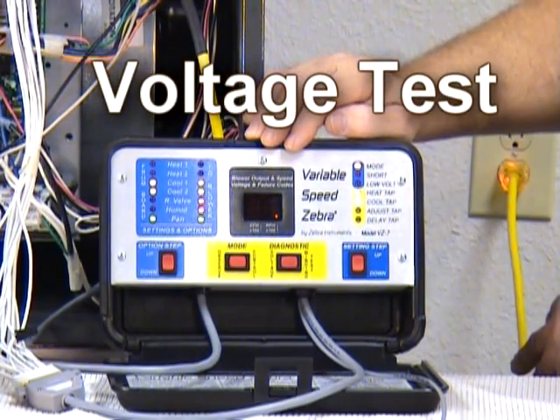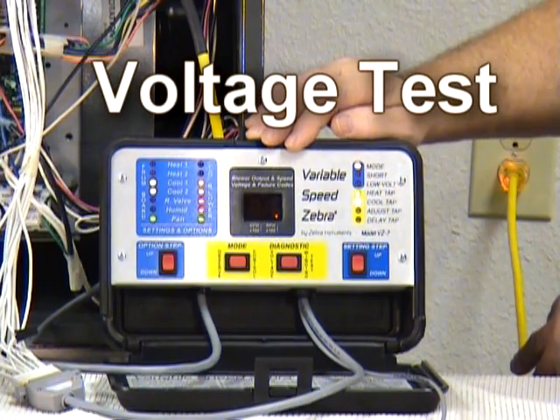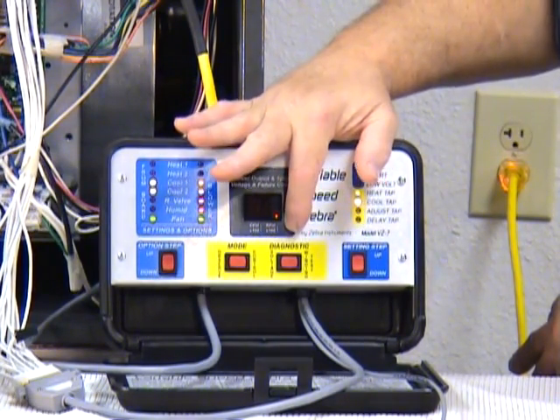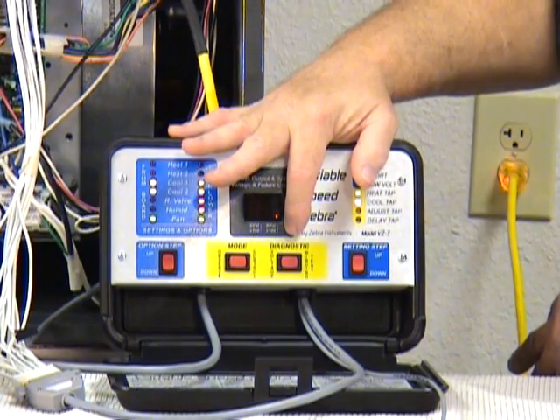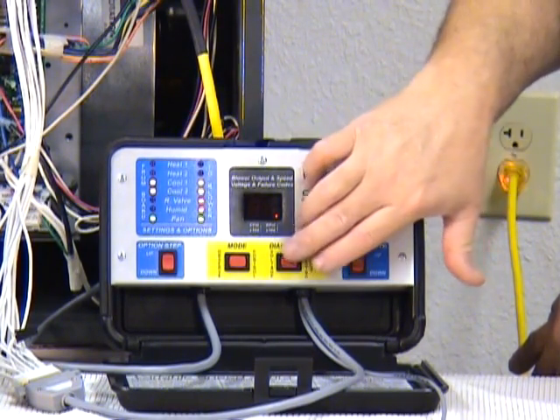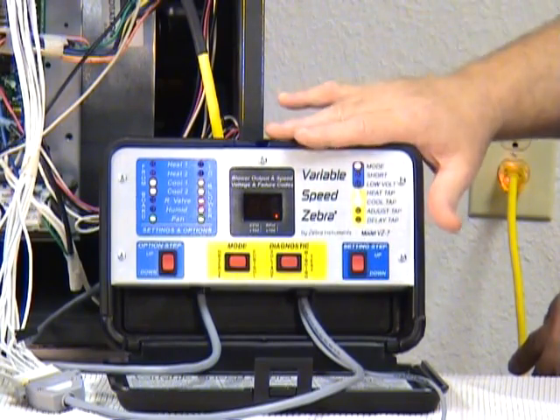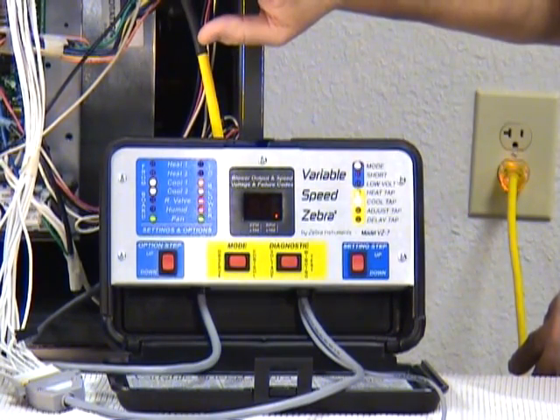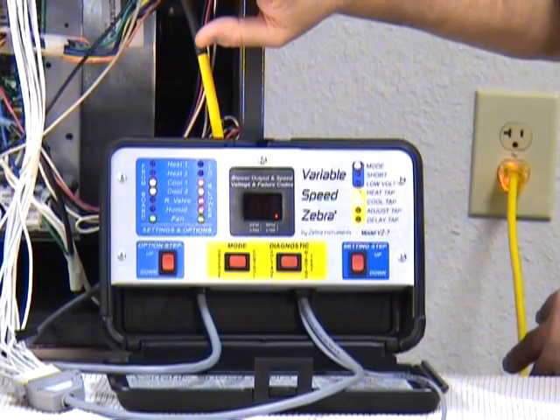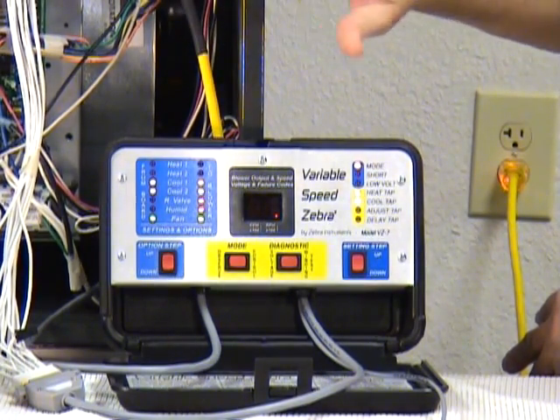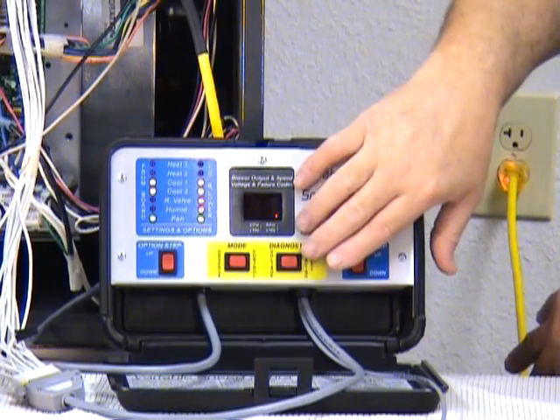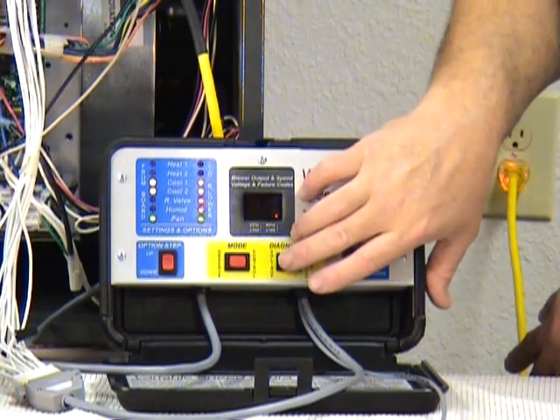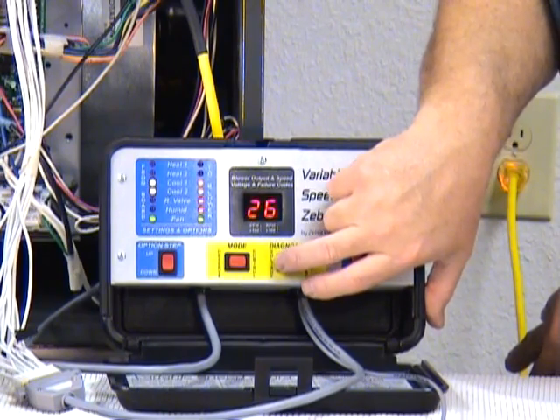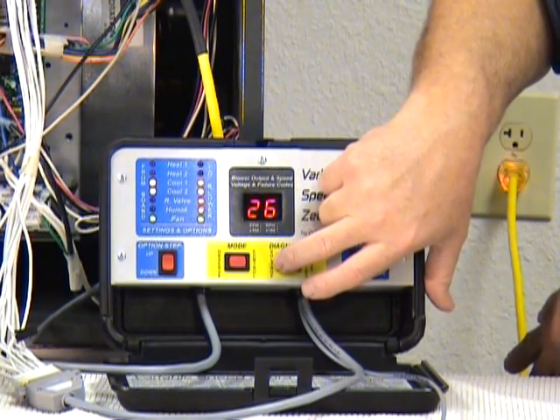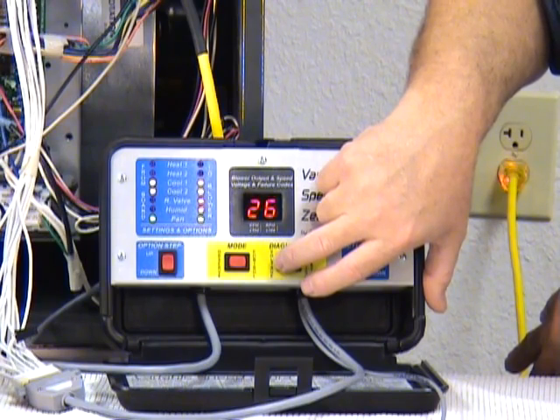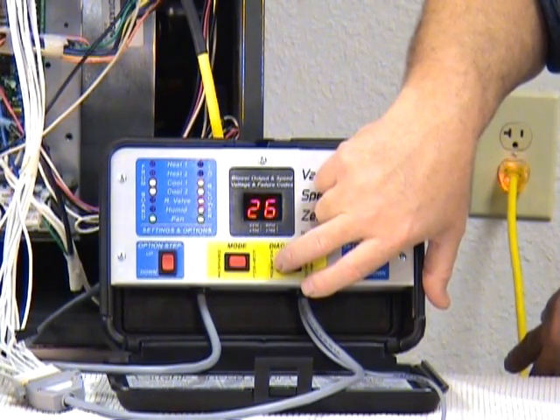A couple of other things you need to know about the variable speed zebra: there are two other features available to you here to use in diagnosing your system. The voltage line. A lot of people don't stop to think that a transformer could have a problem and be producing low voltage or high voltage or something that would interfere with the system. We give you the ability to monitor that voltage by pressing and holding the side of the switch that says voltage. This particular system at the motor is receiving 26 volts of power, which is just fine.